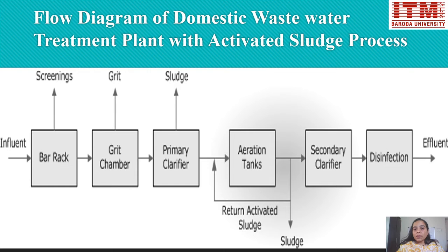And if at all it will be required, then chlorination is the most techno-economical solution, because by jar test you can determine the optimum dose of coagulant to be added in the coagulation chamber. Same way, by breakpoint chlorination you can determine the optimum dose of chlorine which should be added in the tank for chlorination of that quantity of wastewater. So disinfection, I will say, for this particular domestic wastewater treatment plant is an optional step. We have to take the decision according to the quality of wastewater.